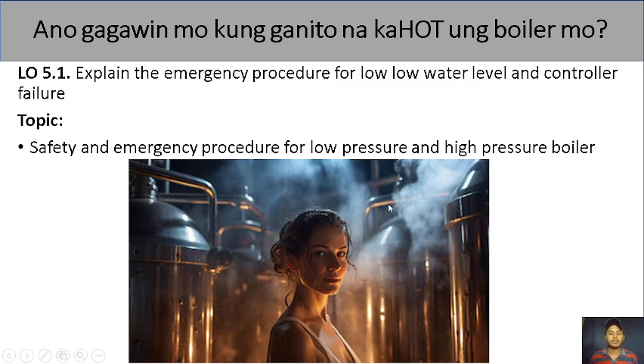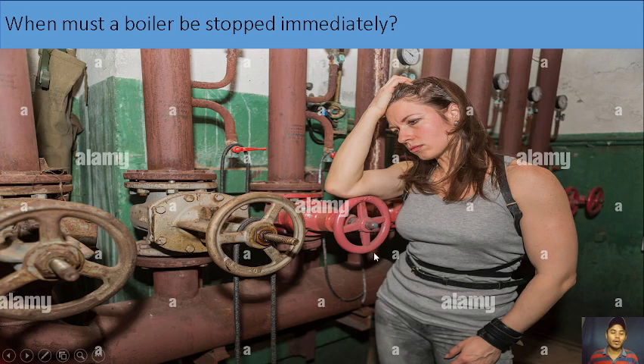Okay, so let's talk about safety and emergency procedures for low pressure and high pressure boilers. So if the boiler is like this, would you still leave it? It seems not, right? Okay, so let's go. When must a boiler be stopped immediately? Think, when must a boiler be stopped immediately? There are different scenarios or occasions when you should stop the boiler immediately.